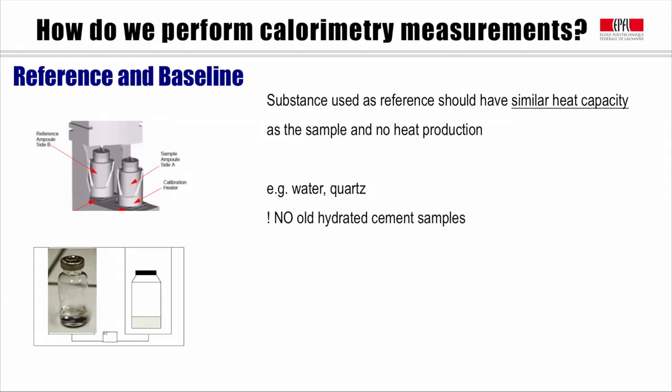First thing we need to do now is to select a reference and prepare it. The principle for choosing a reference is that the reference should have no heat production during temperature change. Commonly used references are water and quartz sand. Please remember do not use old hydrated cement samples, since the hydration of cement even when it is matured will not be ended completely.